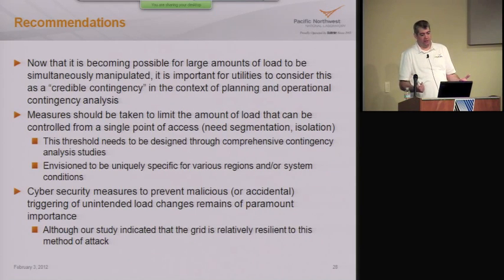There's a lot of assumptions that need to go into that. When I talked earlier about the credible contingency analysis that utilities do, both from a planning and operations standpoint, now that it's possible, or soon will be possible, for large amounts of load to be manipulated through cyber means or some other mechanism, it's important for utilities to appreciate that possibility and include it within their suite of scenarios, because it varies seasonally and based on loading profiles. It's impossible to come up with a single answer saying as long as you can't shed more than X, you won't have a potential problem with cascading failures.